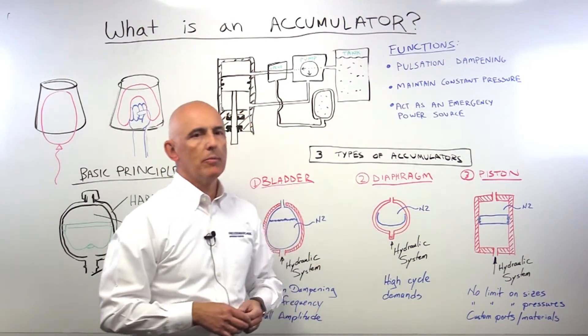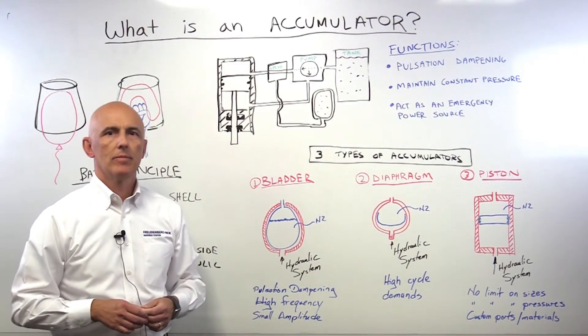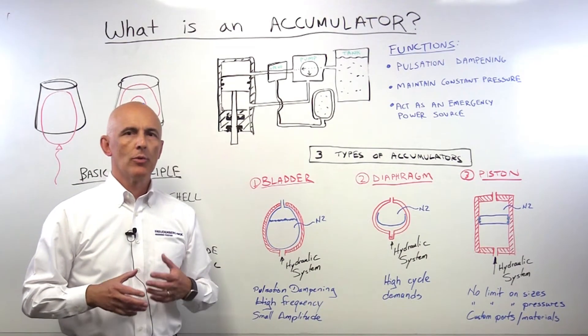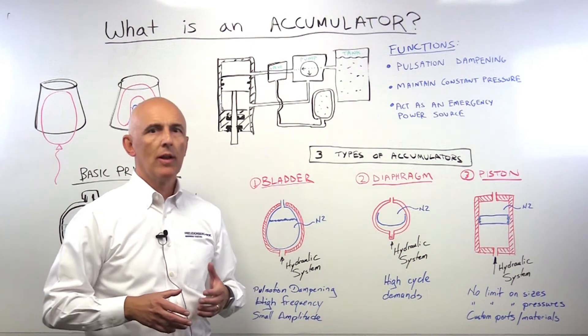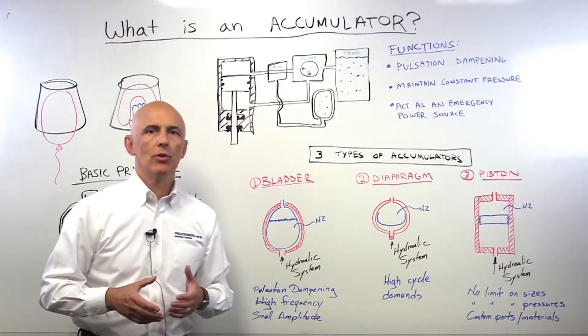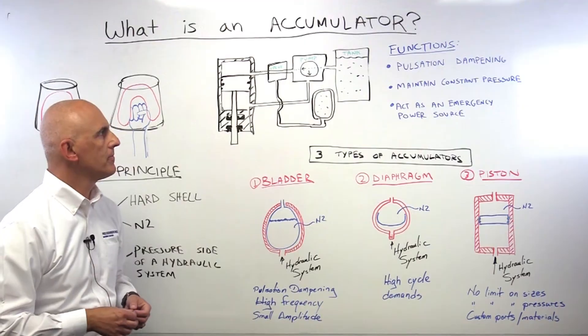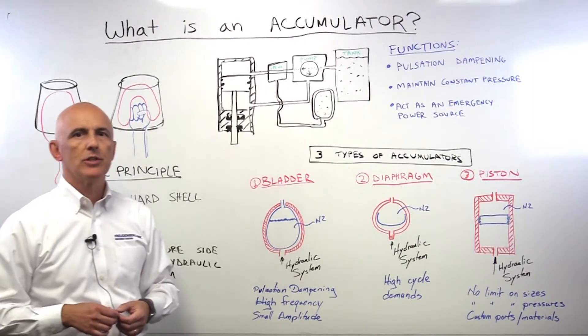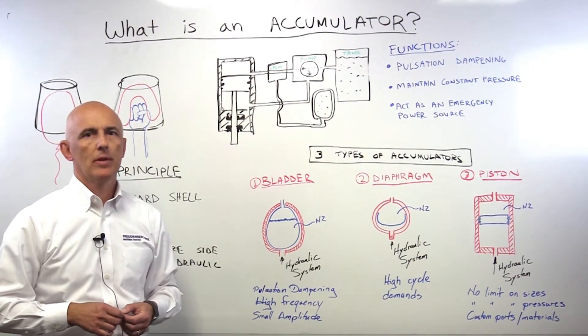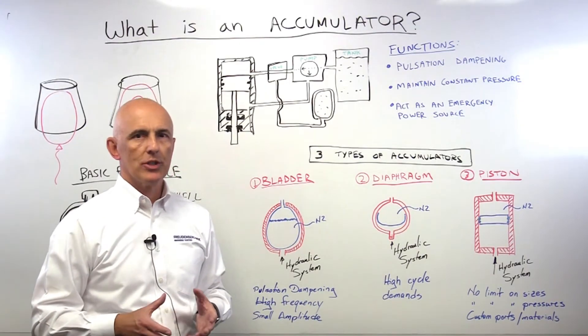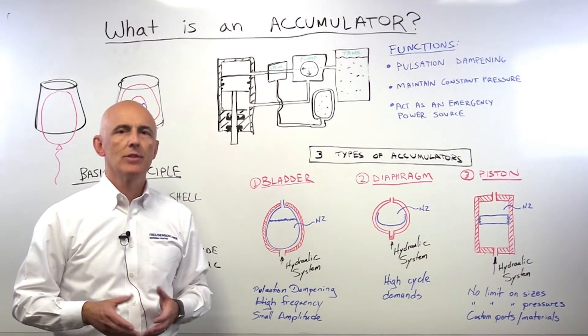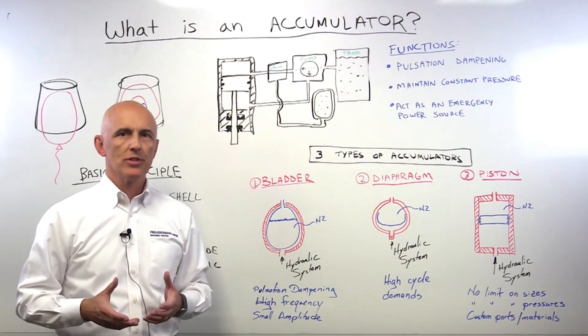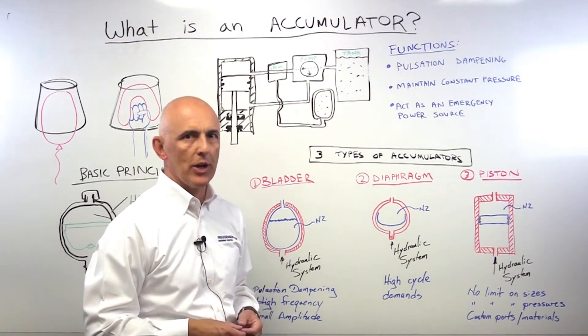Also, the accumulator can keep constant pressure in your system. If you have a leakage, for example, you're going to lose the pressure of the system. The accumulator will stabilize the pressure and keep it at a certain level until you can stop your system for maintenance. Another function for the accumulator is to be an emergency source of power in your system. For example, when your system is applied on hydraulic brakes and you need a sudden release of pressure, the accumulator will help you releasing this pressure whenever it is needed.